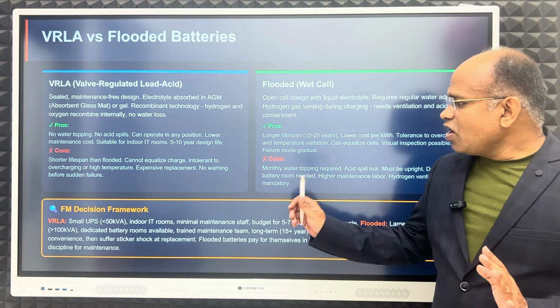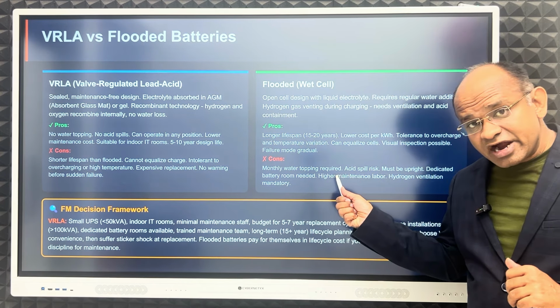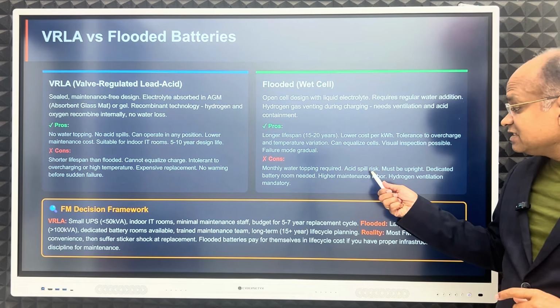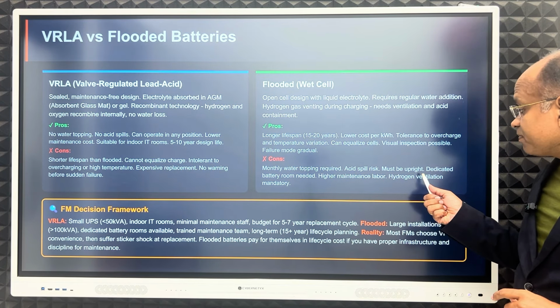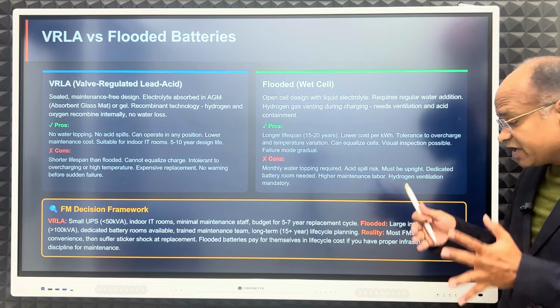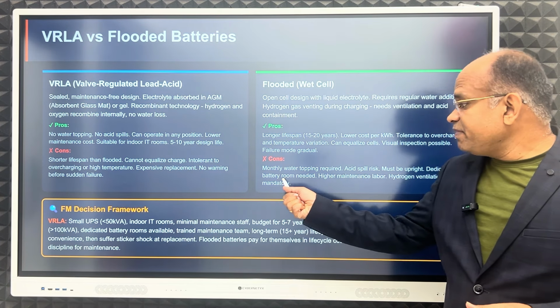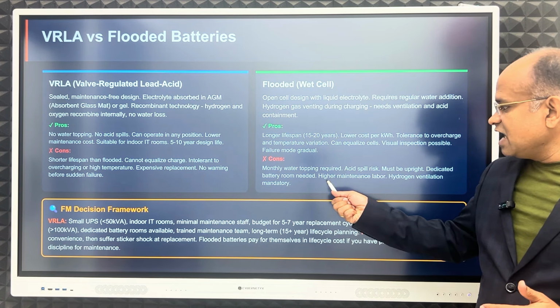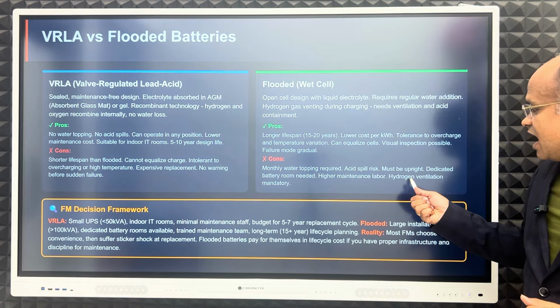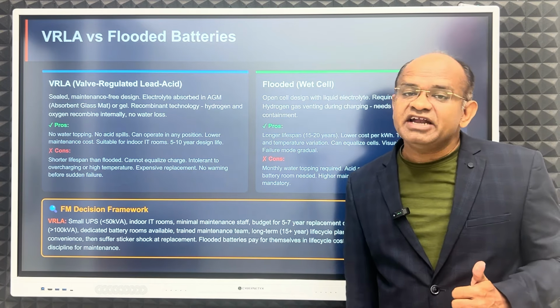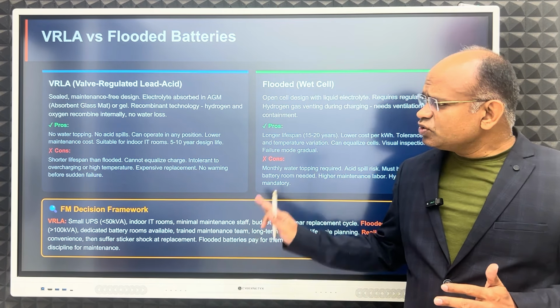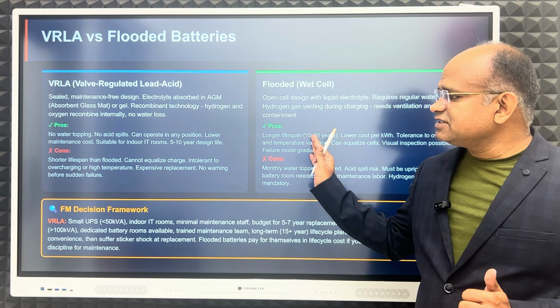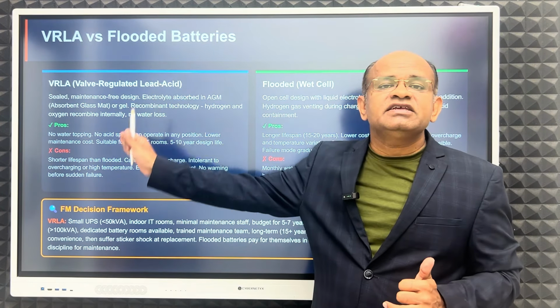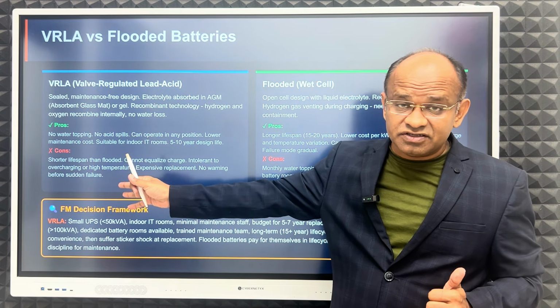Now the cons: monthly water topping required every month, acid spill risk, must be upright/straight, dedicated battery room needed, higher maintenance labor, hydrogen ventilation mandatory. So these are the cons of flooded cell batteries, but these batteries have been used for so many years.